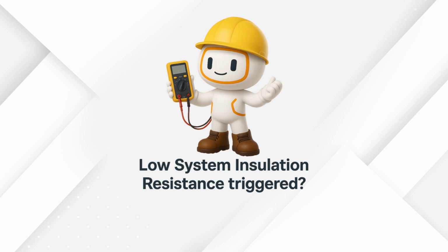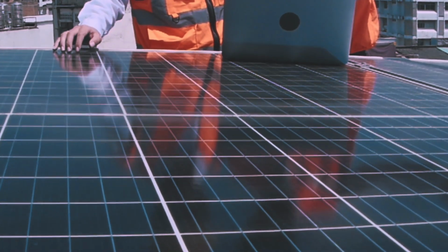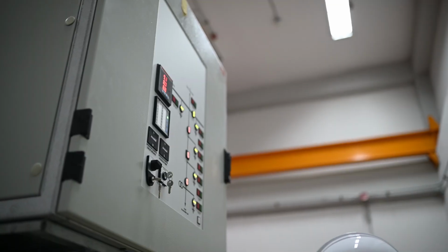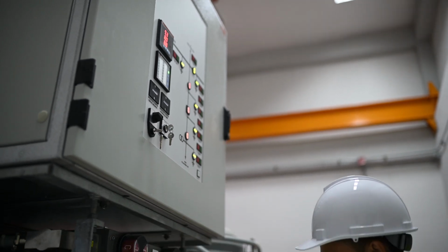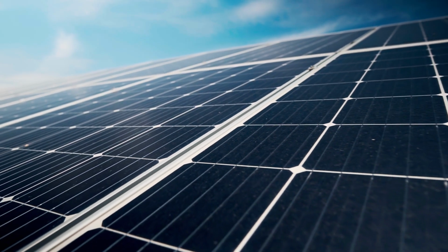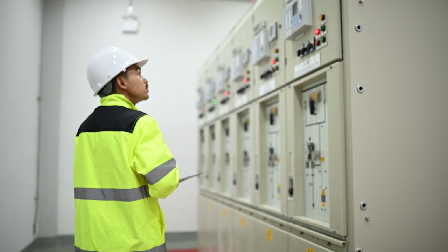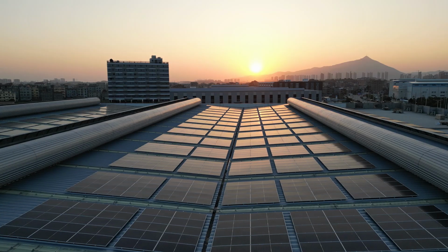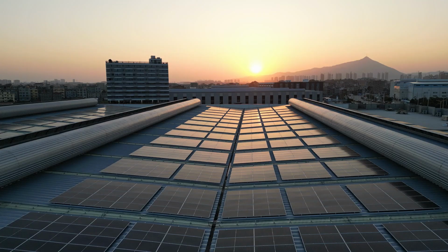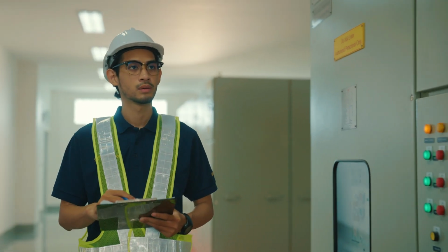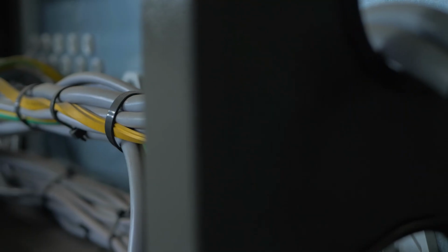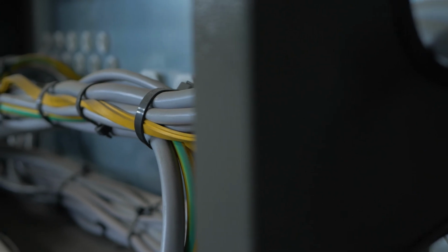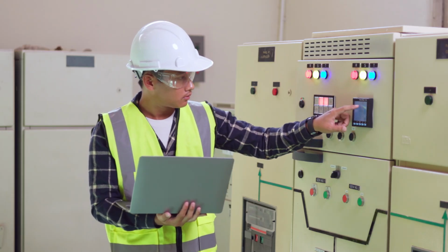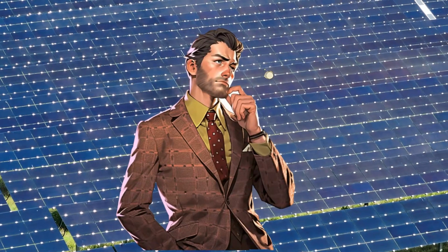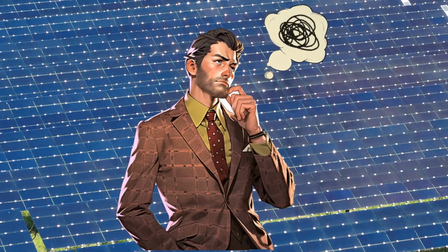Today, we'd like to share a real-life case from the field. One installer reached out to us because their inverter wasn't running. After some remote analysis, we discovered the issue was related to insulation resistance, and the root cause turned out to be a damaged DC cable. In this video, we'll walk you through how we detected the issue, what steps were taken, and how you can troubleshoot similar faults on site.